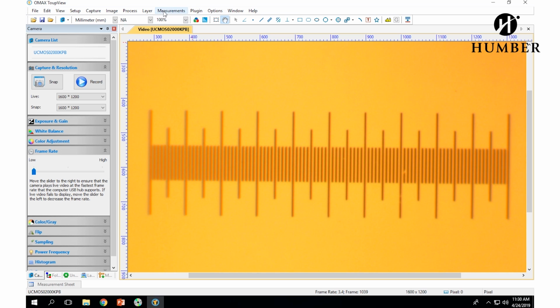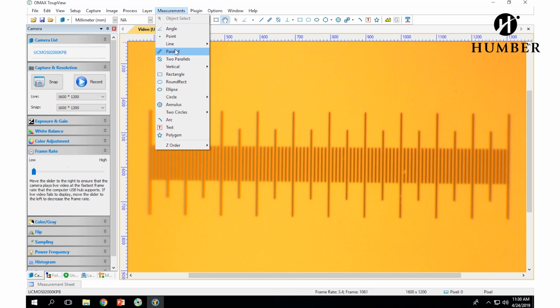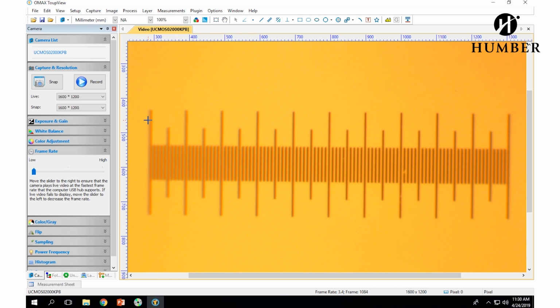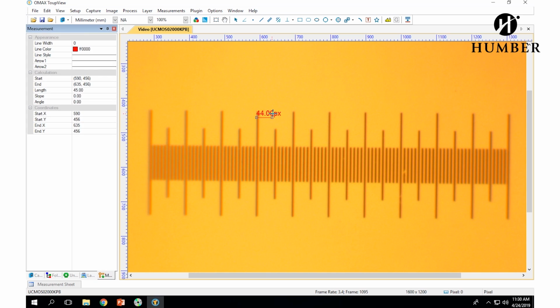Let's actually test it and see whether it is working. So you go on to measurements, you click on line, and for our sake now just click on horizontal line, and you can start measuring. Say you want to measure, and maybe you can select any number of lines. You want to make sure you have selected the correct length, and you can see this is 10, 20, 30. So you can see how accurate this microscope is in terms of calibration. So you could have selected any amount of lines.